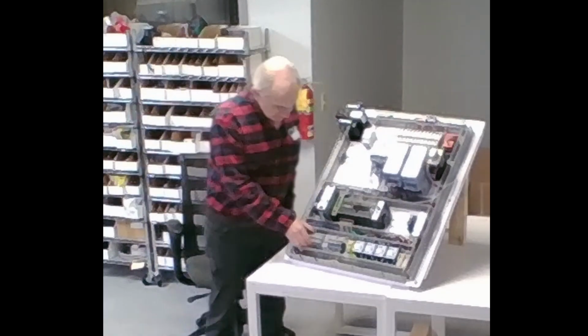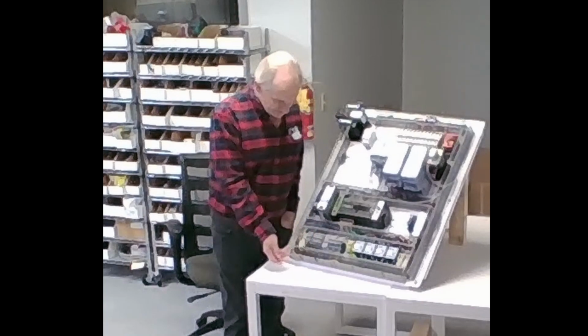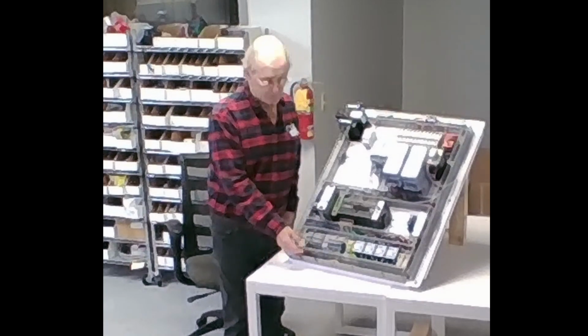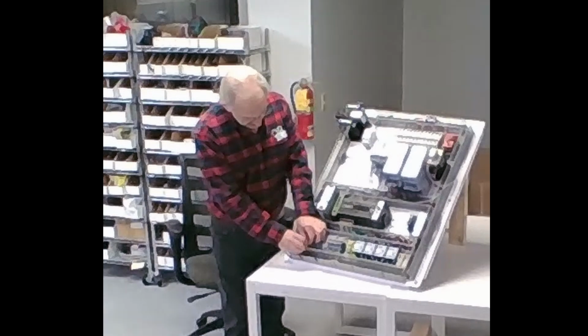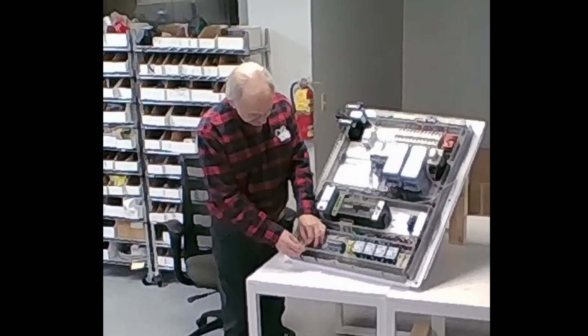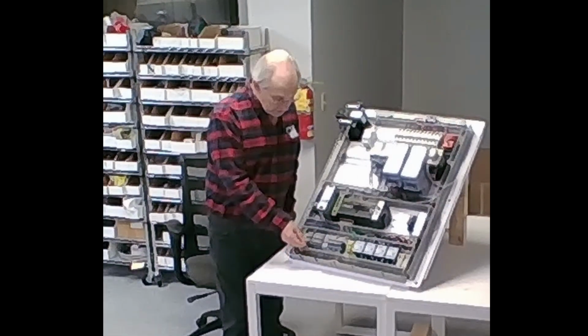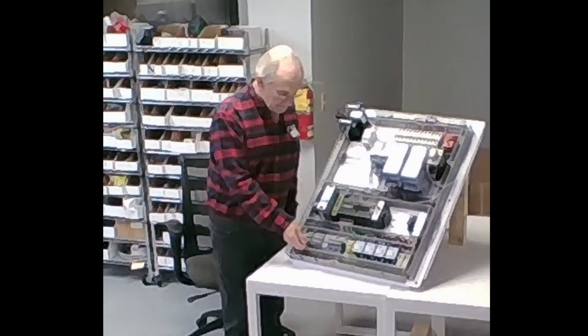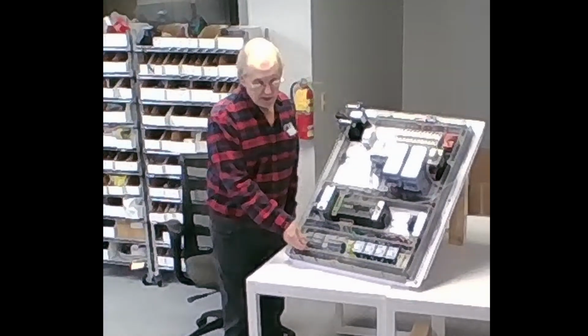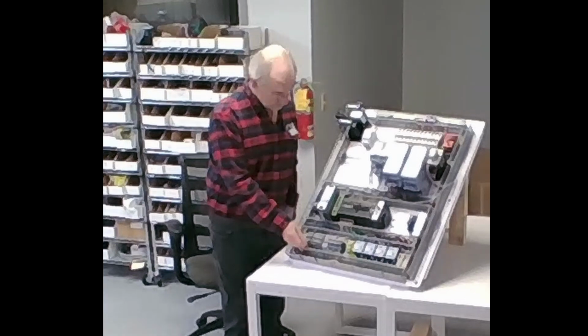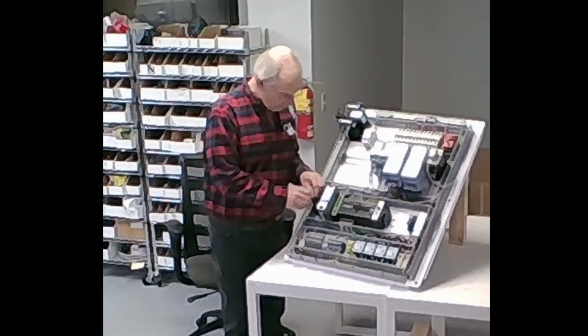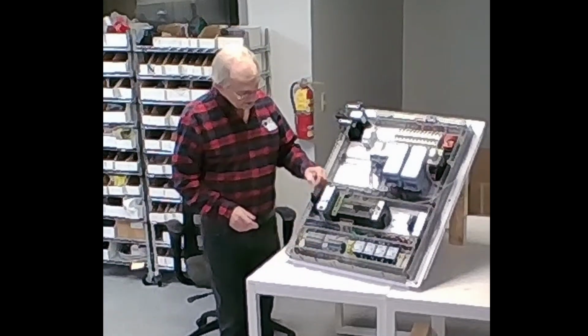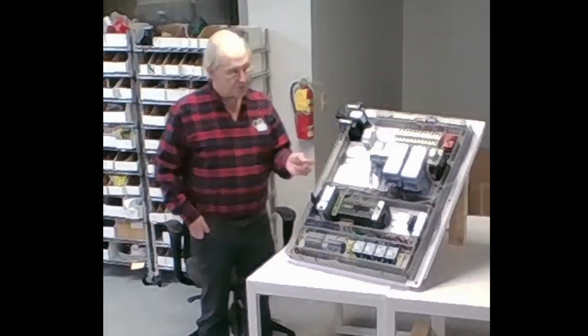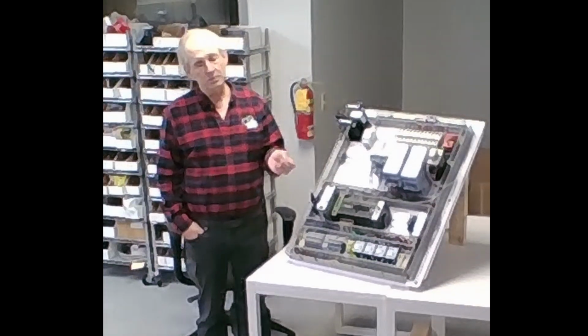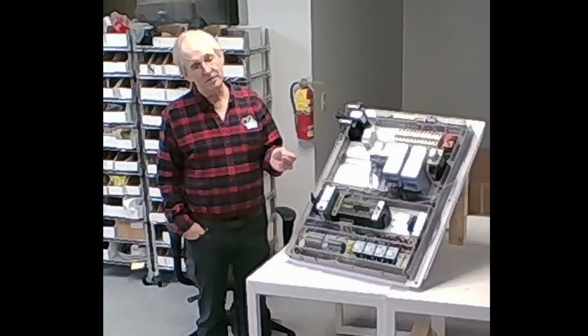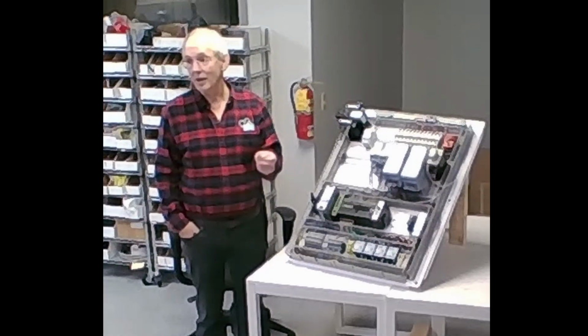And so down here we have small fuse holders that handle a smaller fuse. Now, we use these little tiny fuses, the 5x20s. I use them on the DC circuits. That again is not an absolute requirement. I could use the larger 1/4 inch by 1 1/4, but the reason for the difference is I like that when you pull up on a fuse, you know you're looking at DC versus AC just by the fuse size.